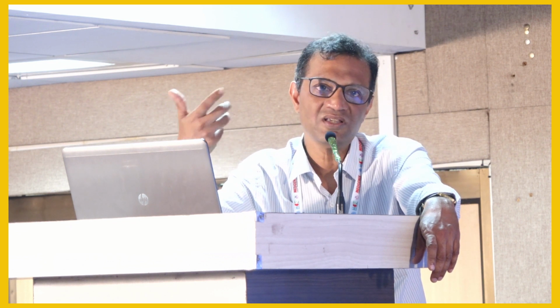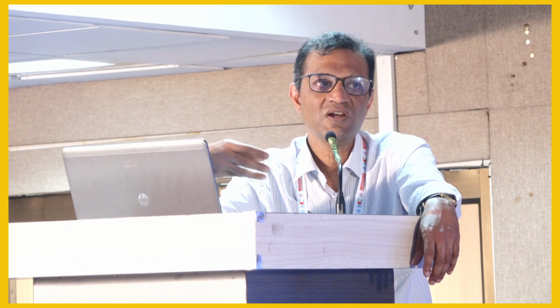So all I needed to do in that sense was to insist that the minimum you must do is to rinse a machine between two treatments. The rinse cycle of the Fresenius machine is about 16 minutes. A hot disinfection is 35 minutes. So in busy units like you are saying, they may not be able to do hot disinfection, but at least a rinse should be done. Ideally, if you can do a hot disinfection after each shift, it's great.